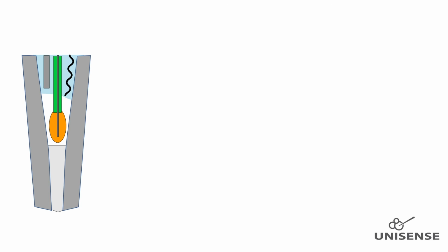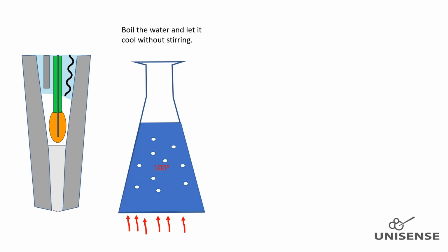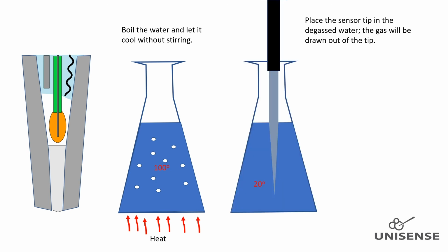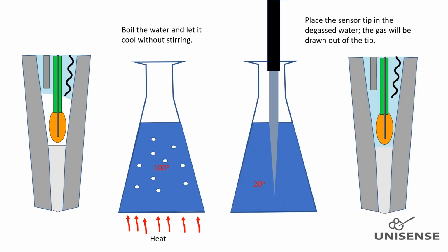Such a gas phase can easily be removed by inserting the tip into degassed water, which will drag the gas out of the tip through the membrane. Fill water into a glass bottle and boil the water. This drags gases out of the water. Let the water cool to room temperature or below without shaking the bottle or mixing the water. Place the sensor tip into the water for some hours. The gas will be removed by this procedure.